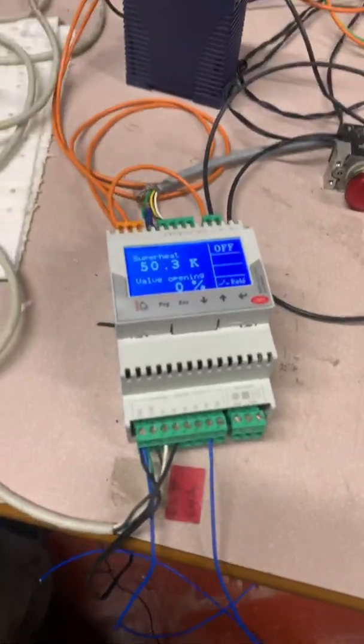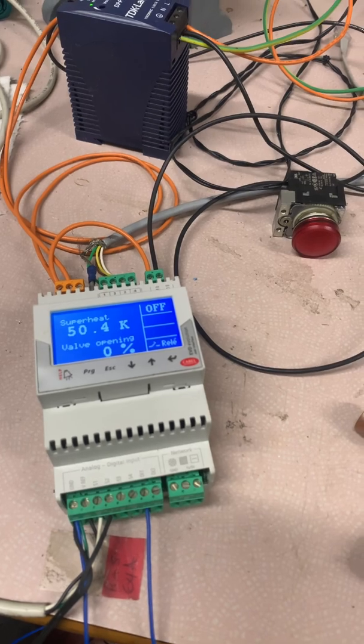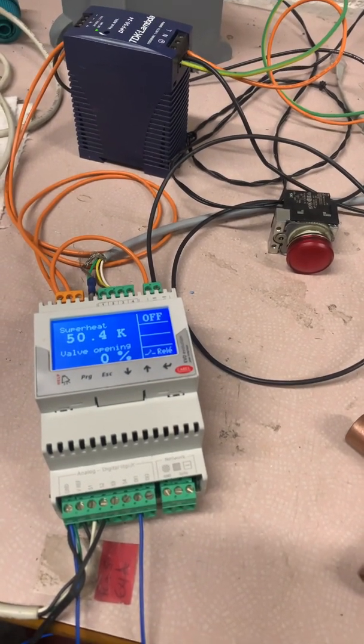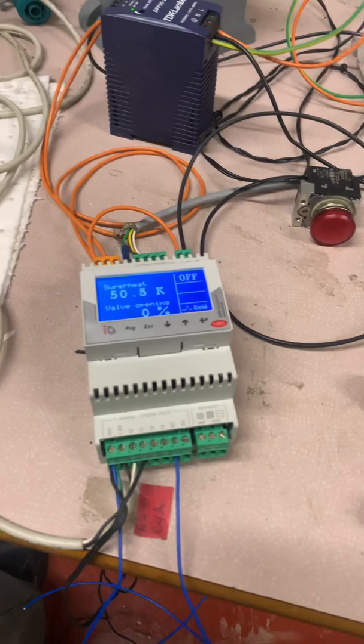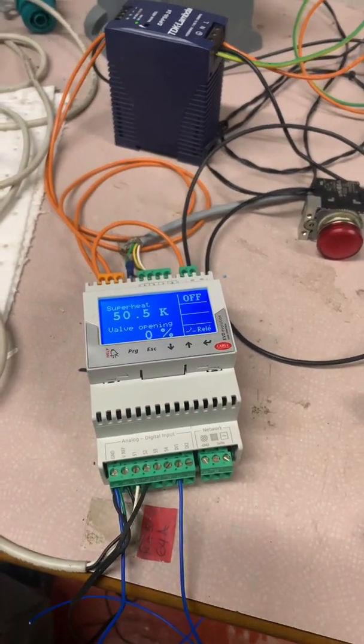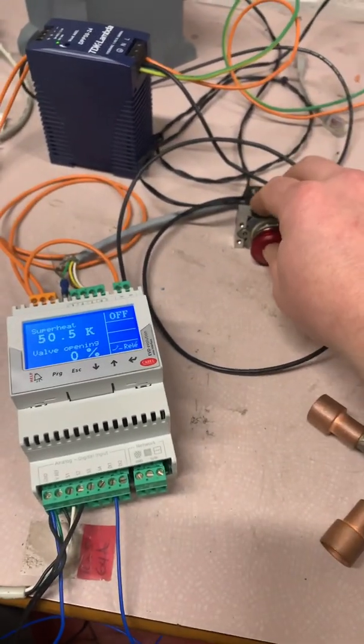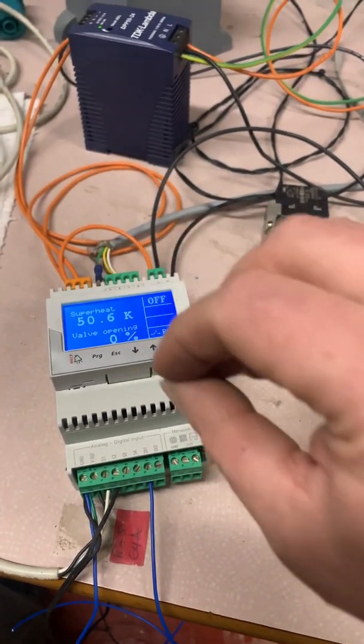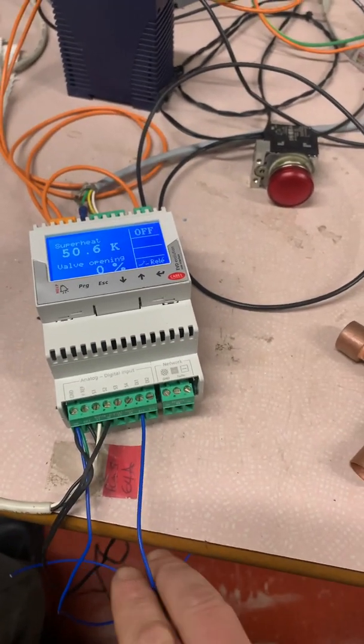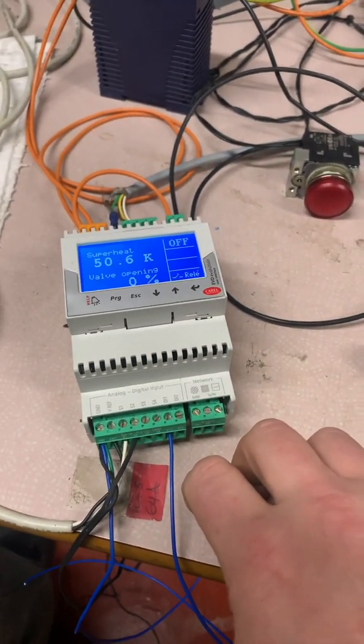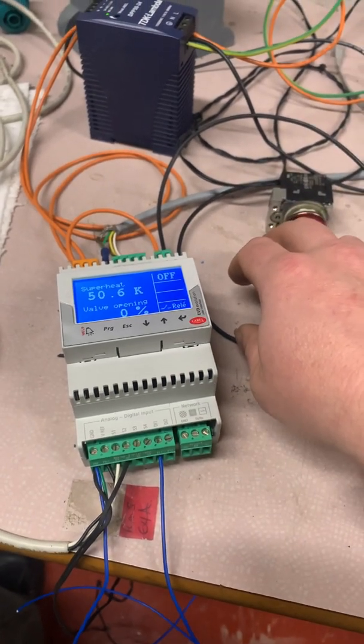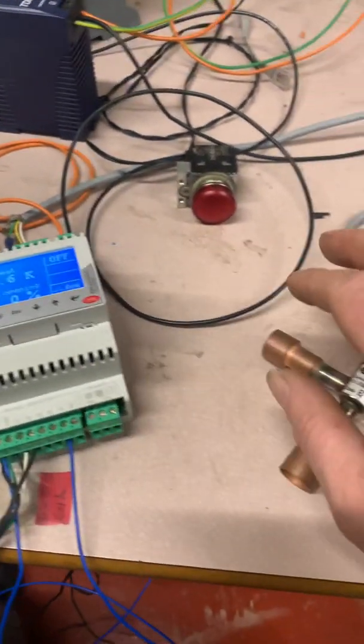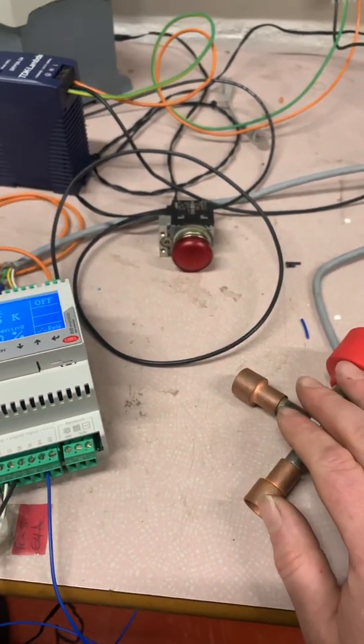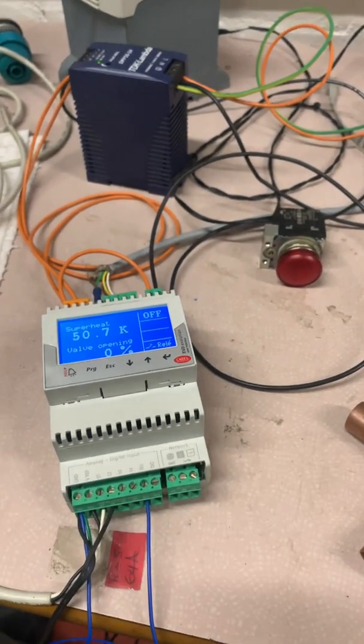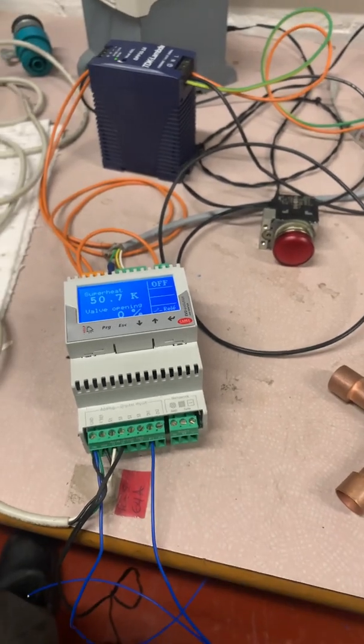All right, so that's how it would work. And if you ever lost the pad, the reason to have your solenoid, which would be here, energised by this, is that if you lose the power, you'll lose the solenoid. And you don't do any refrigeration, which could be a problem for flooding the coil. So there we go.